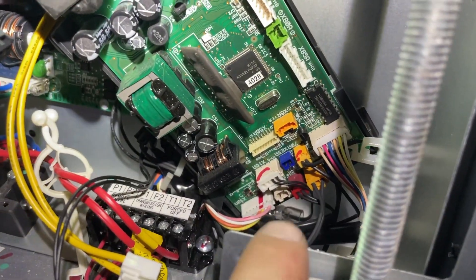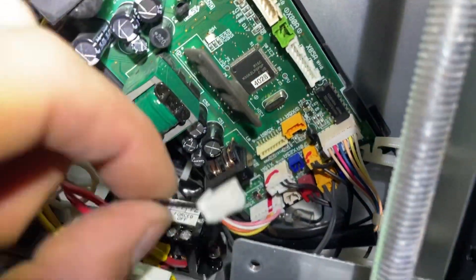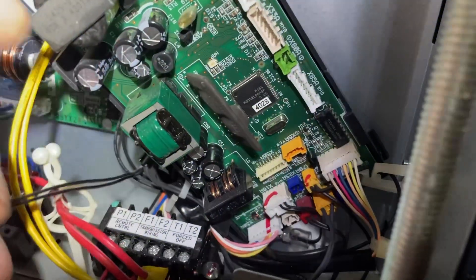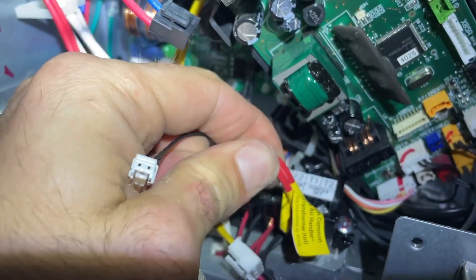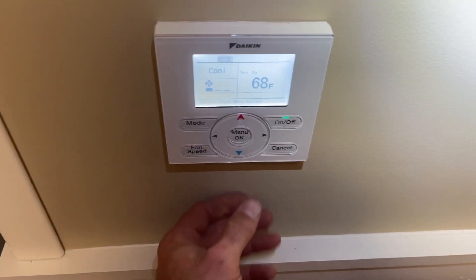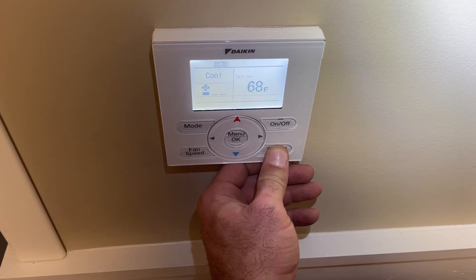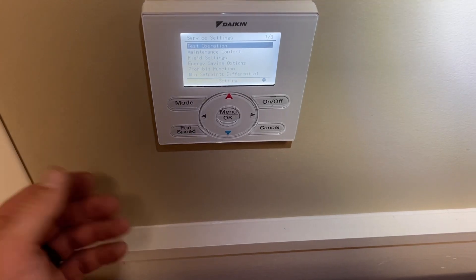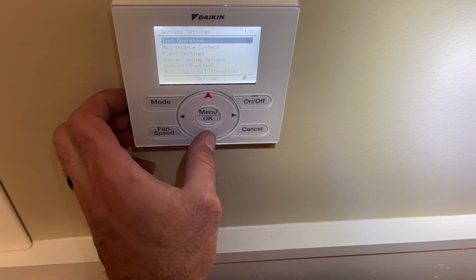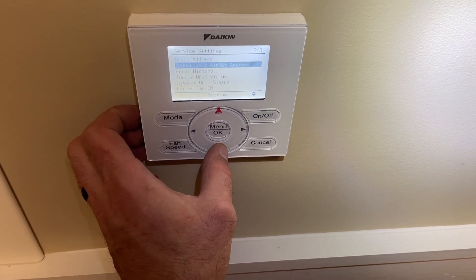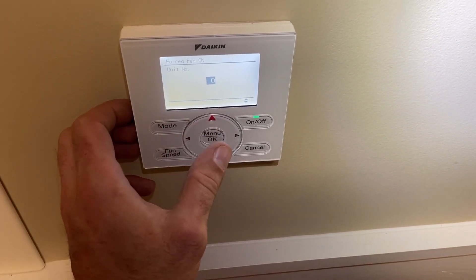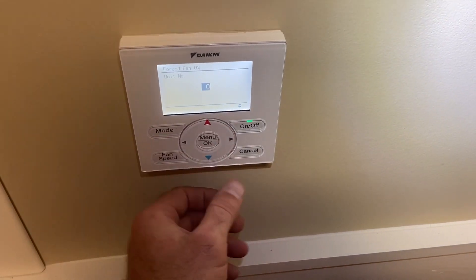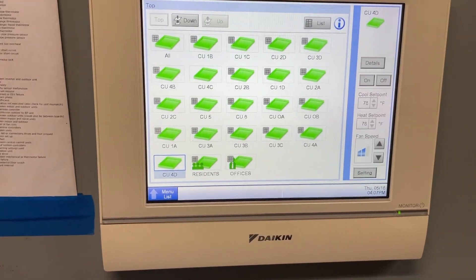It turns out that this is X15A. These units are always hard to work on — just not made for American meat hands. This is the factory float switch, right in there. A great option would be just to break this with that right there. Let me show you one more thing that's very helpful: to make sure we're on the right unit for this air net, we force the fan on like that. I can hear the fan running up there, so this nav does go to that unit that we've been working on.